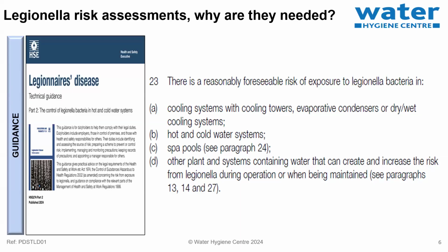But the likelihood is that there's going to be something, whether it's being operated on or maintained, there may well be an aerosol, and it's up to the site's responsibility or the system owner to identify what those systems are before the risk assessment. And the risk assessor should take into consideration how it's operated. They should get the expertise of the people who are using the equipment to make sure that they understand how it's managed, how it's being run on a daily basis, and how it's being maintained. So those four things there, it's the catch-all statement at the bottom from within the HSG 274 document, which means any other risk system.